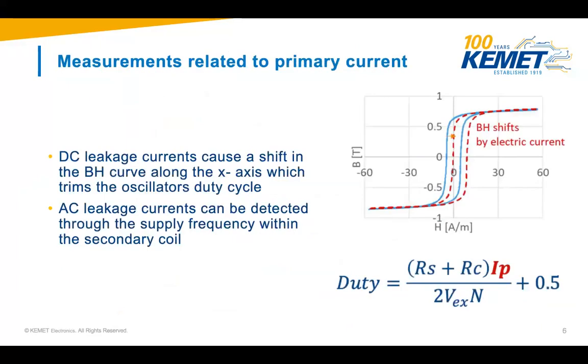So how do we do this? These measurements are related to the primary current, and every magnetic material has some influence when you overlay a DC current, meaning you shift across the x-axis by the electric current. So you change the behavior of the BH curve, and with the oscillator we can define this as a duty cycle. If it's 50-50, there's no leakage. If it's varying, then we have either a minus or a positive leakage.